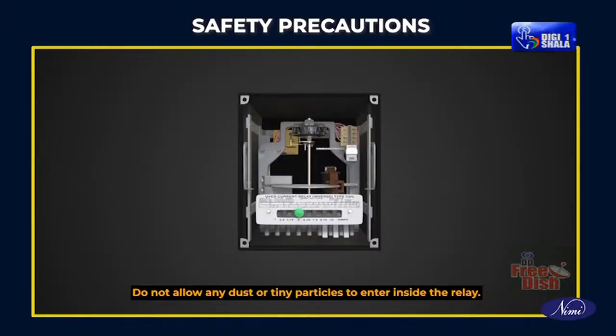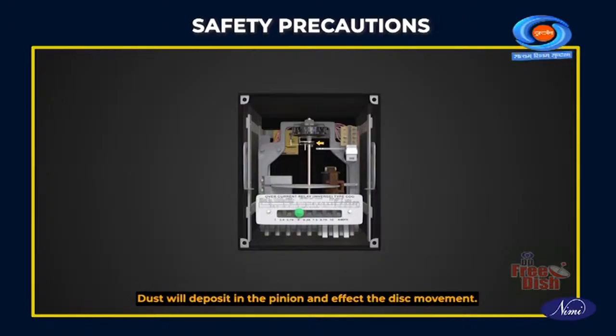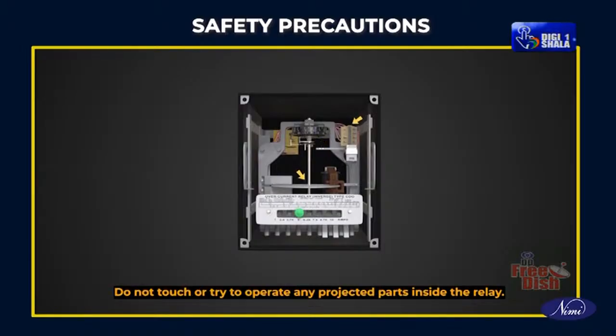Do not allow any dust or tiny particles to enter inside the relay. Dust will deposit in the pinion and affect the disc movement. Do not touch or try to operate any projected parts inside the relay.